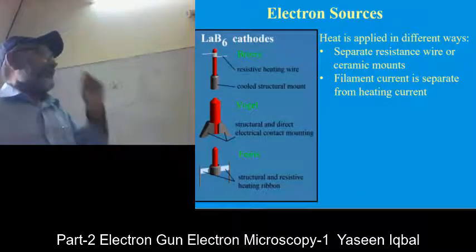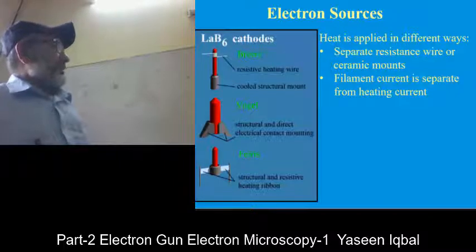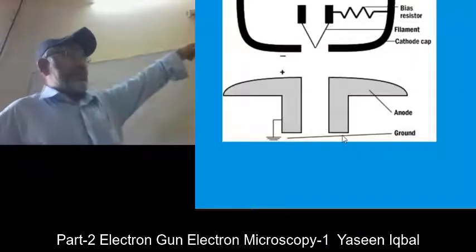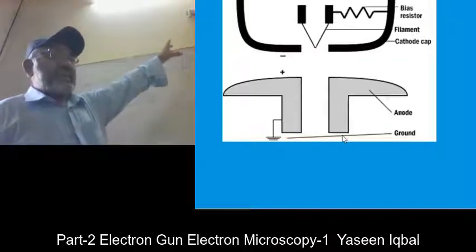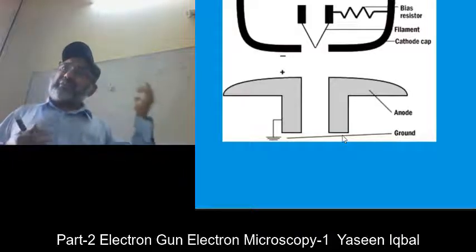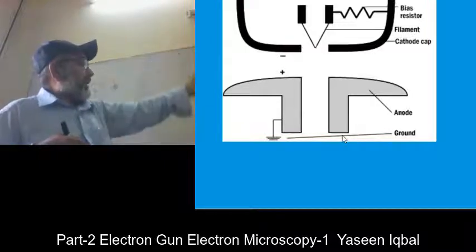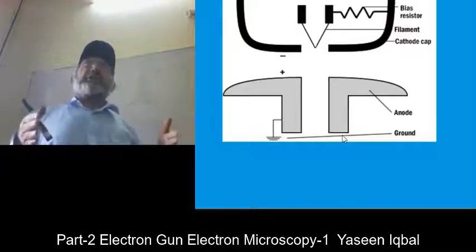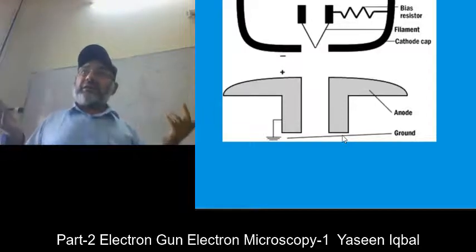Lanthanum hexaboride filaments are of different shapes, and heat is applied in different ways — either via a separate resistance wire or a ceramic mount. The filament current is separate from the heating current. The filament tip is V-shaped, and a resistor heats it a little bit. This is the cathode. When electrons are released from the filament, you need an anode to pull the electrons down toward the positive electrode, and then you control them with electromagnetic lenses, which are coils of metallic wire.